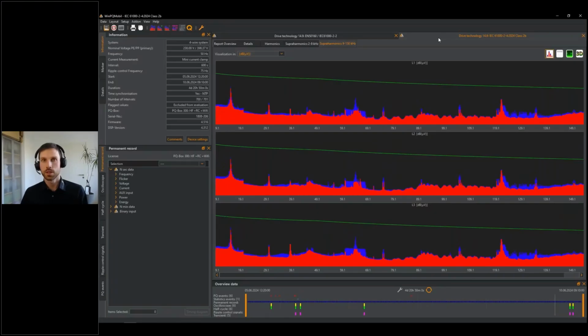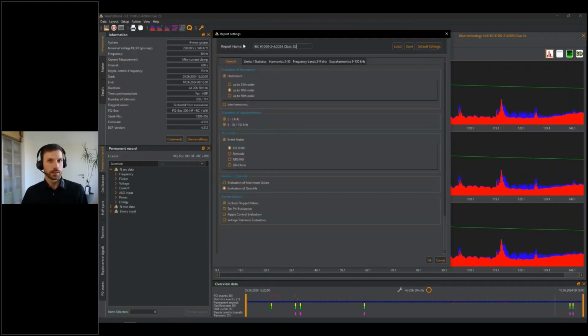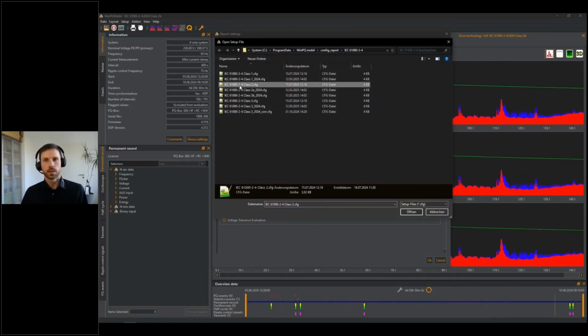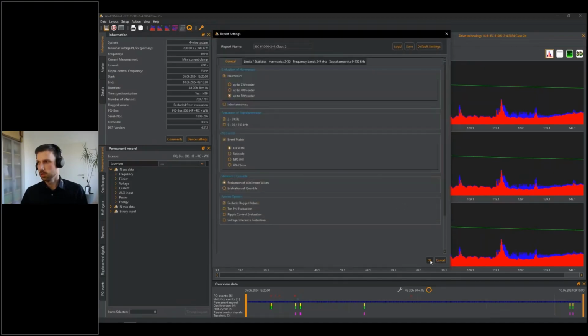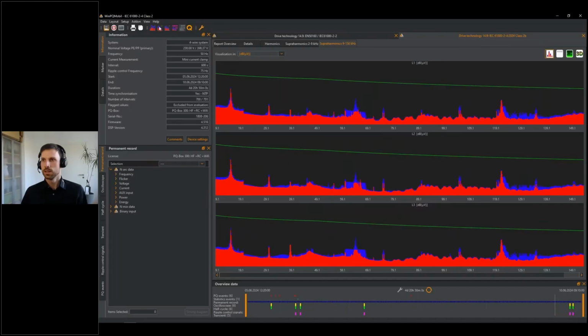And it's even more different if I open the old standard. So I will go to the report setting again, and just as an example, I will load the old class 2. I click on open, and what immediately stands out is that the tick for 9 to 150 kilohertz is missing, because the old standard did not cover frequencies above 9 kilohertz. I click on OK, and I do the norm evaluation again.